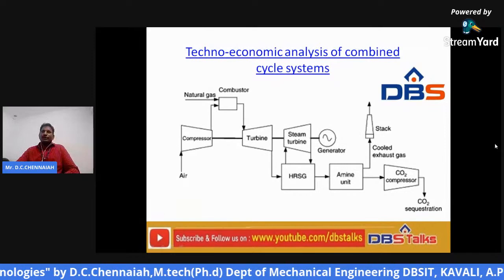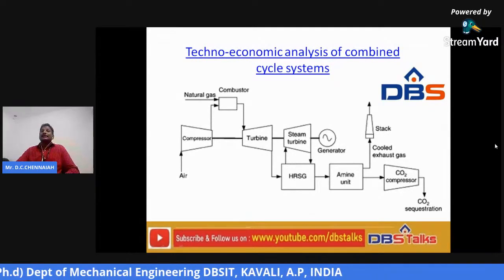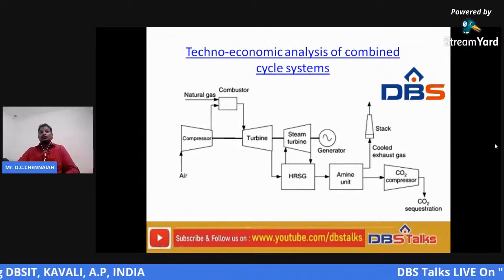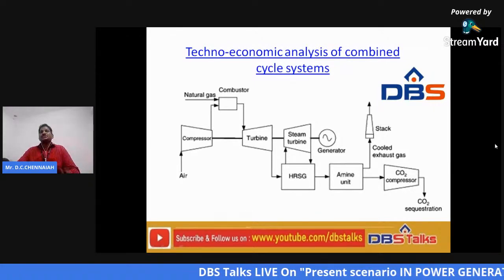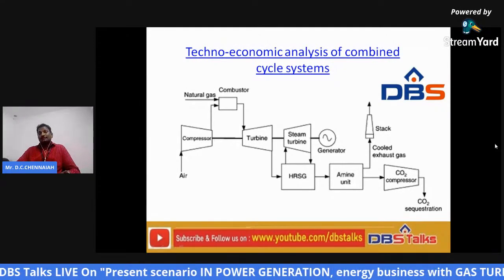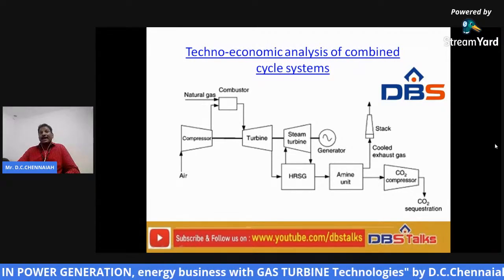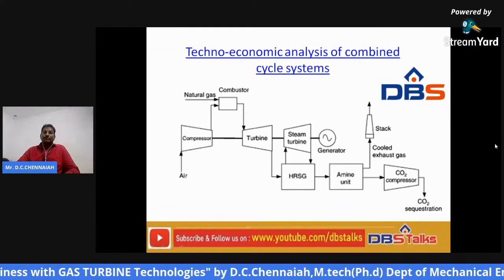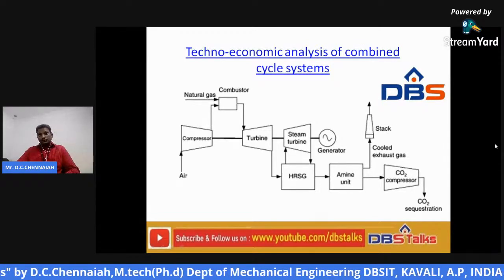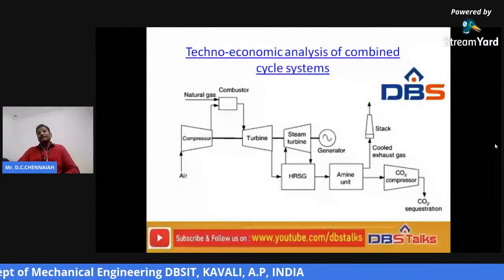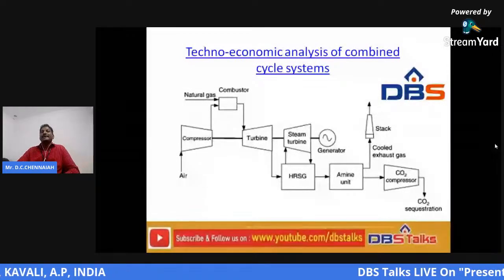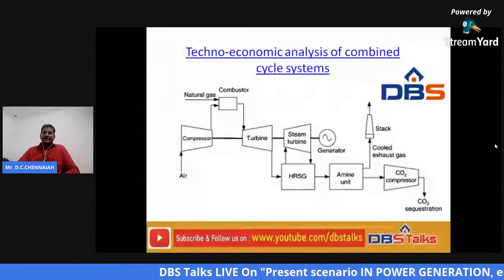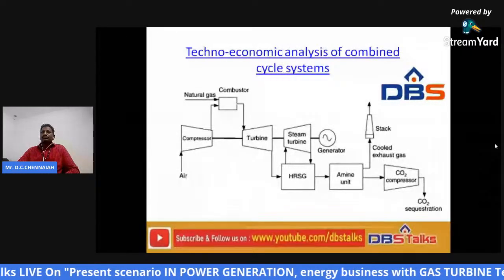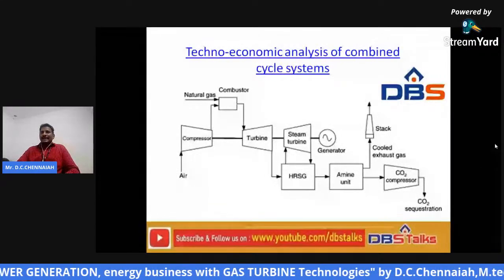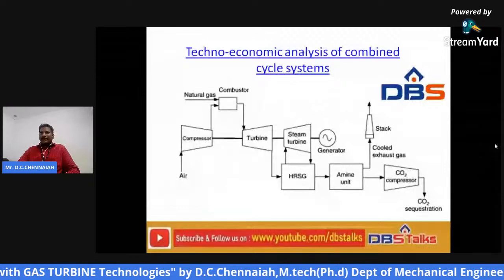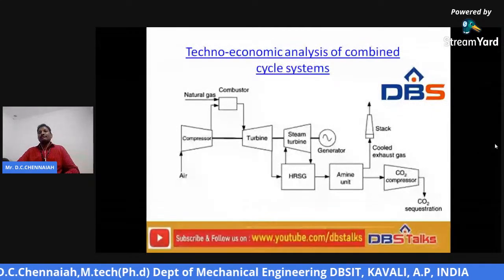Once the fuel burns completely, its entire heating value, the entire heat energy, will be released in the combustion chamber. As the released heat increases to maximum, the gases reach maximum temperature, and hence maximum enthalpy. So we get maximum kinetic energy, and hence maximum rotational work, which is transferred to the shaft, and the generator produces a heavy amount of electrical energy.